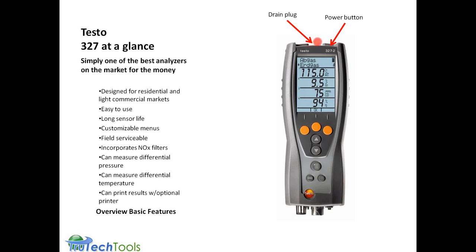It's mildly acidic water. It's got about the acid content of orange juice, so don't worry about getting burned with it. It won't eat through clothing or anything. You can put it down most community drain systems. But be sure to close the drain plug. If you don't close the drain plug, you've just made a pathway into the meter for room air. And room air will dilute the sample and throw off all your gas readings and most of your calculations in the meter. So you don't want to do that. If you open the drain plug, make sure you securely close the drain plug afterwards.